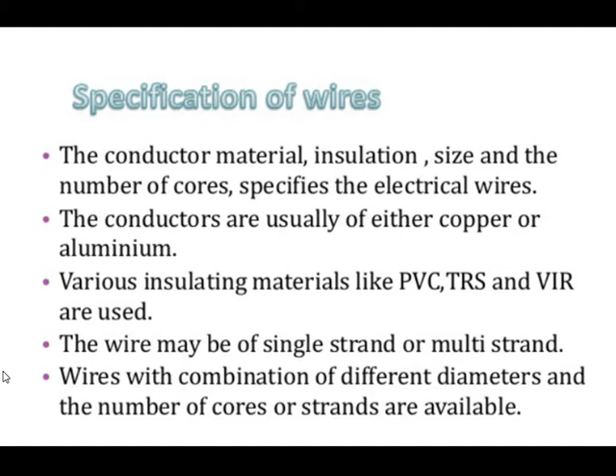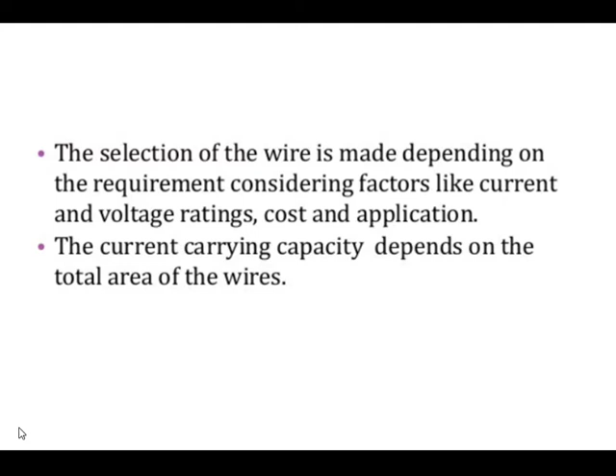And the selection of the wire is made depending on the requirement, considering factors like current and voltage rating, cost, and application as discussed earlier. So the selection of the wire mainly depends on the current rating of the particular equipment, the voltage rating of the equipment, and the cost and application, that is, for which purpose it is used. And the current carrying capacity depends on the total area of the wire. We know that the current capacity of a conductor mainly depends on the cross-section area of the wire. The current density J is equal to current divided by area, I by A. So the conductor cross-section area is the main parameter for the quantity of current.